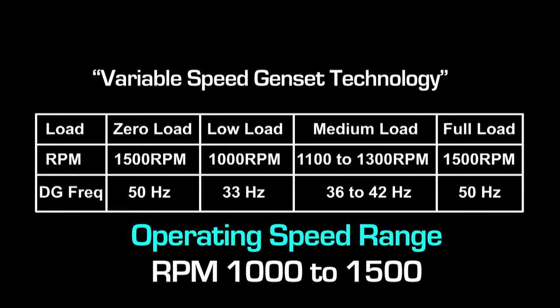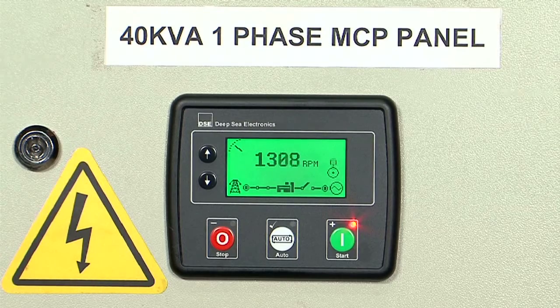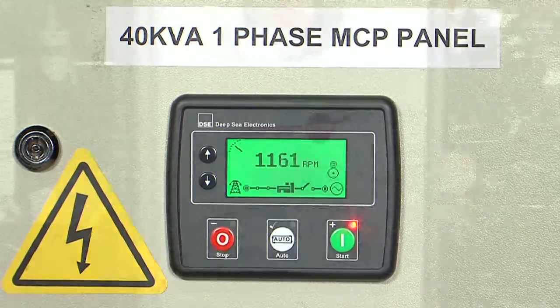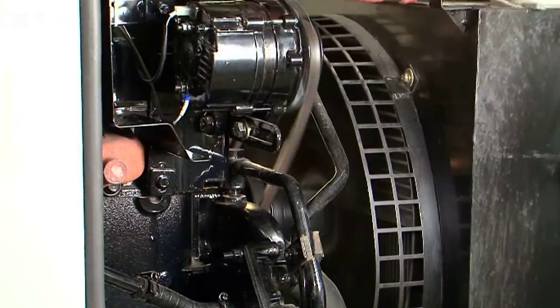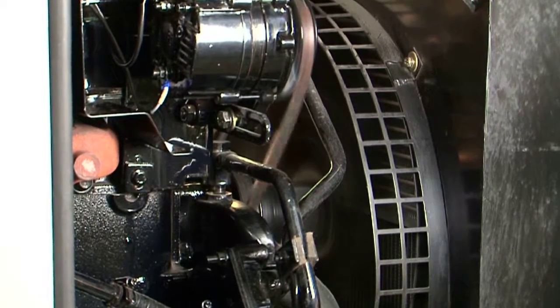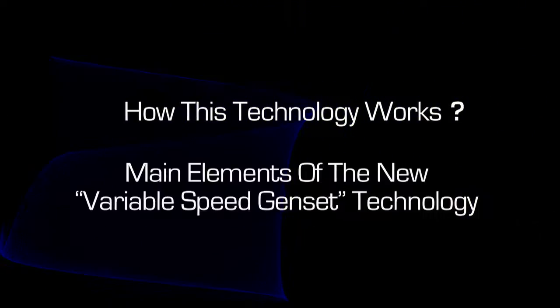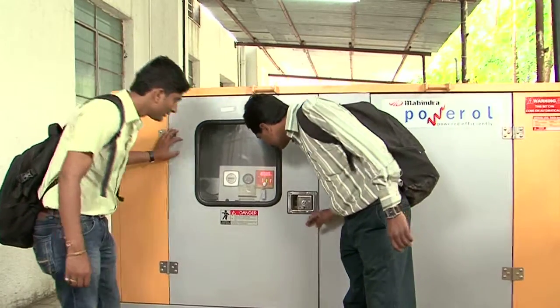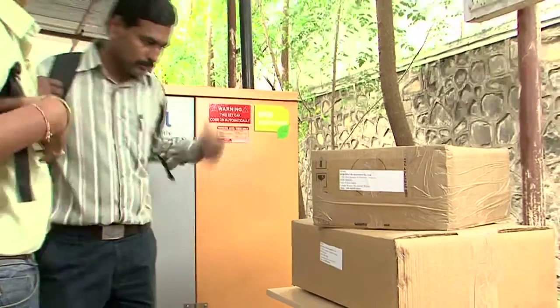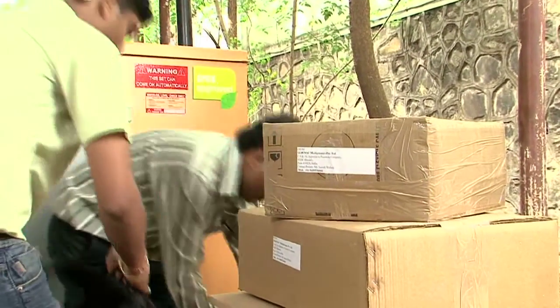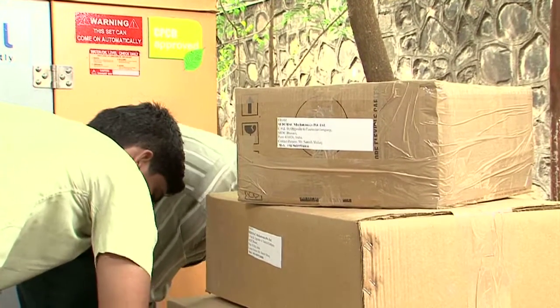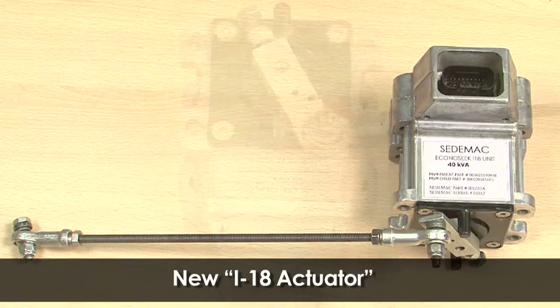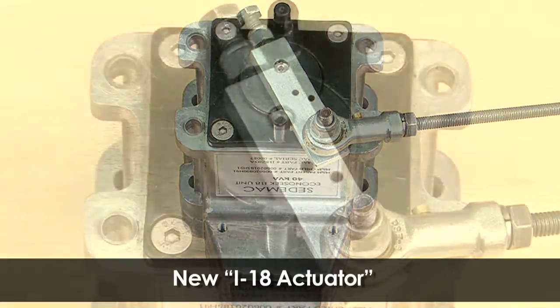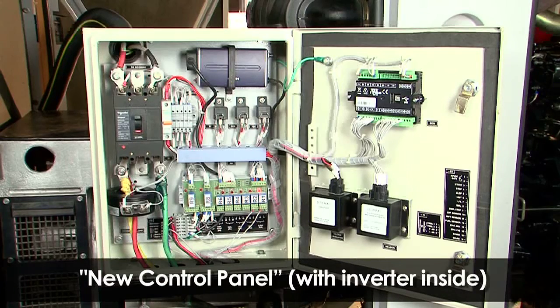The operating speed ranges from 1000 to 1500 RPM. Due to this load-sensitive variation in speed, we achieve lower fuel consumption in part load conditions, bringing in good direct savings. In addition, the wear and tear of the engine reduces and its life increases. Now, let's see how this new technology works and what its main elements are. Variable speed genset contains a special electronic kit which is designed to enable variable speed operation of the DG. This kit is composed of two main components: an intelligent I-18 actuator and a special control panel.